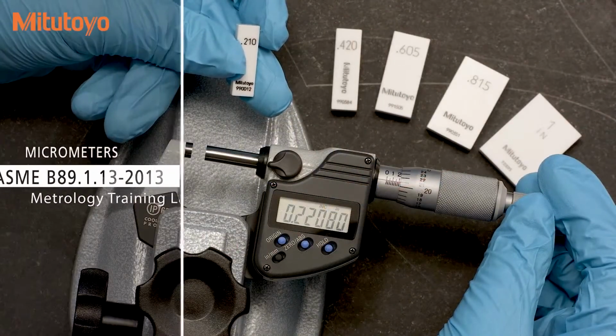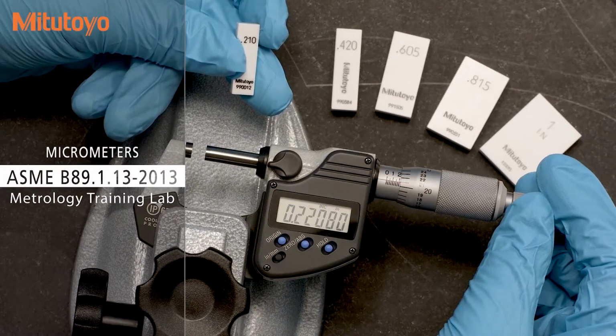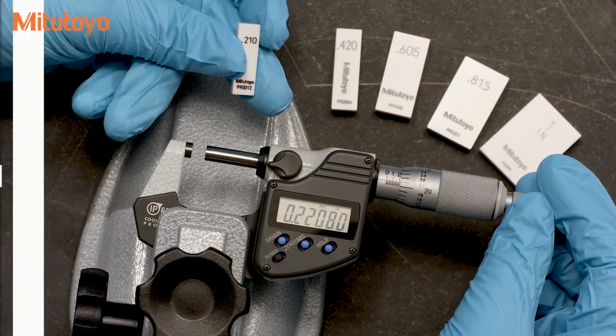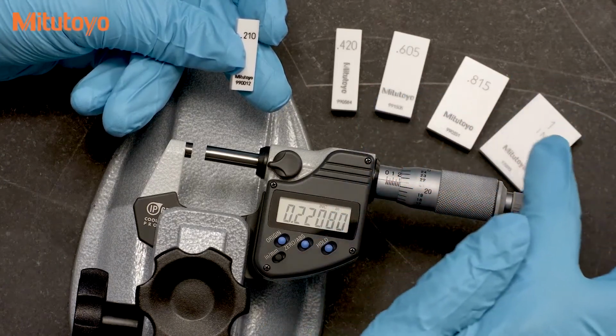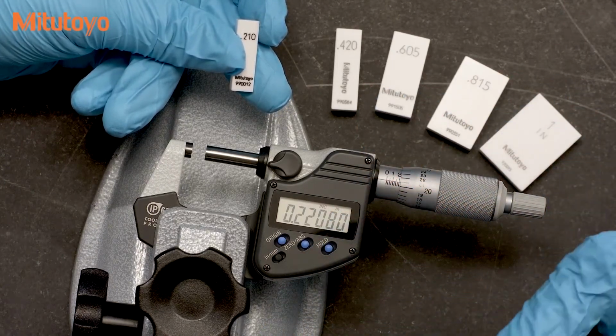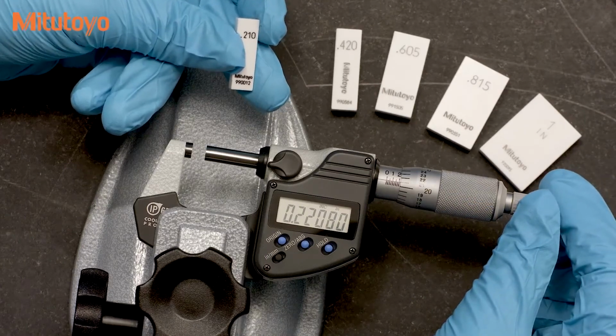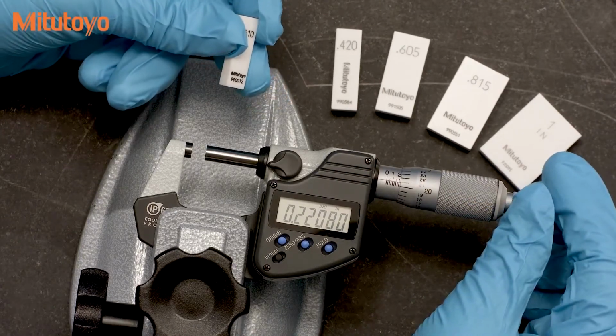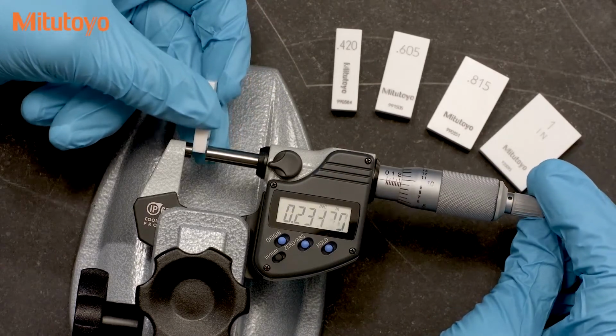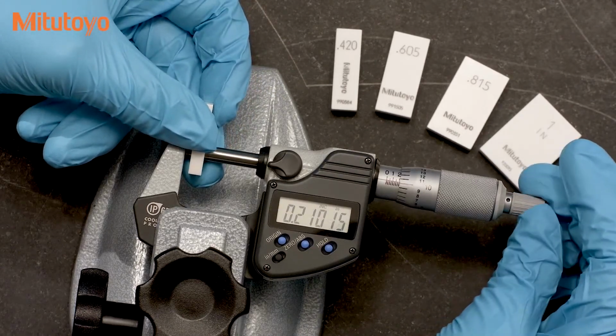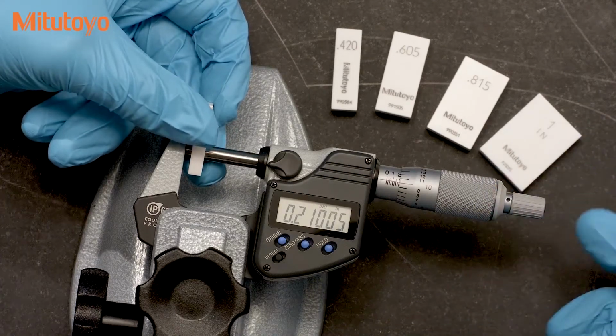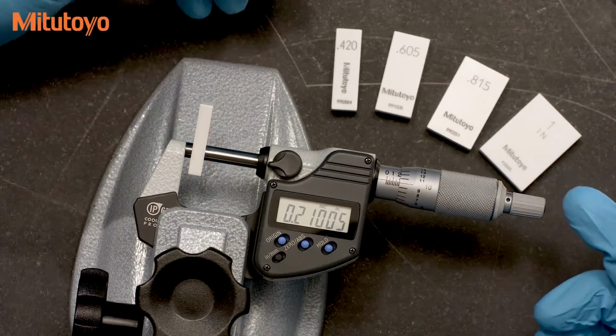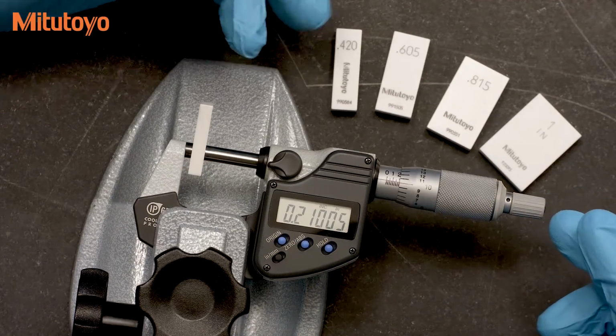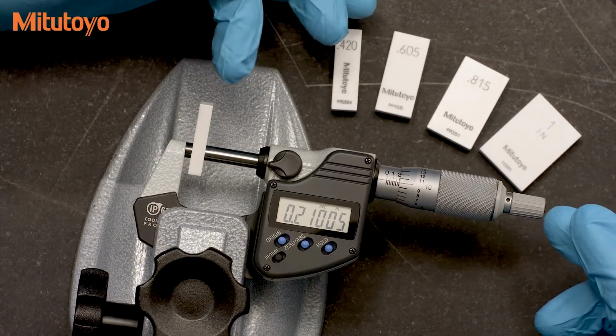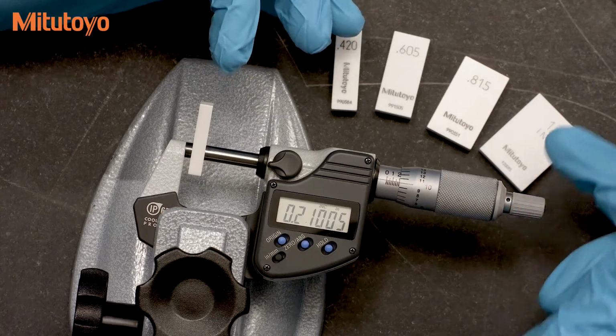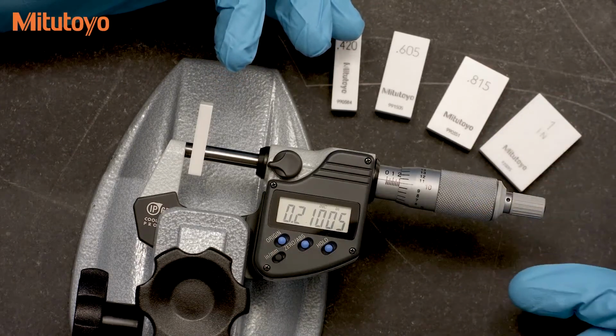For outside micrometers, the ASME B89.1.13 standard recommends 5 specific size gauge blocks for calibration. And these gauge blocks are not commonly available sizes in a standard set of gauge blocks. The reason for these specific sizes is that they will force the micrometer thimble to be in different orientations for each test point. The goal is to have an efficient test that looks for errors across the measuring range simultaneously with errors within a rotation of the thimble.